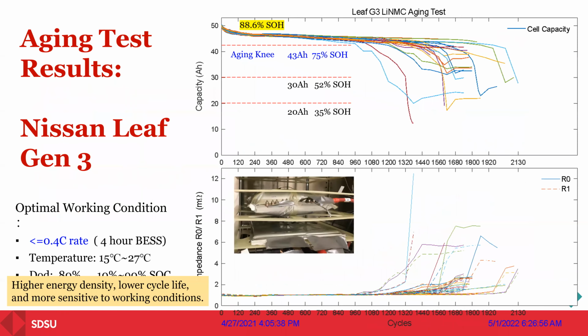For the Gen 3 battery, it is interesting to note that these batteries don't last as long as the Gen 1 battery. They typically last about 1,000 to 1,500 cycles before they experience an aging knee. As you can see from the top graph for the capacity, the aging knee happens very quickly. After the aging knee, the degradation goes very dramatically, so this battery needs to be taken out of service. For the bottom graph, you can see the impedance increases dramatically once the aging knee happens. It is important to identify this aging knee so we can make sure these batteries are taken out of service once it happens, or shortly after, as I'll explain in the next slide.